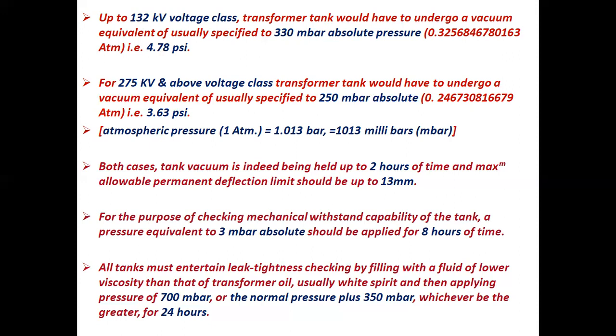In both cases, tank vacuum is to be held up to 2 hours, and the maximum allowable permanent deflection limit should be up to 13 millimeter. For the purpose of checking mechanical withstand capability of the tank, a pressure equivalent to 3 mbar absolute should be applied for 8 hours. All tanks must undergo leak tightness checking by filling with a fluid of lower viscosity than that of transformer oil, usually white spirit, and then applying pressure of 700 mbar or the normal pressure plus 350 mbar, whichever be the greater, for 24 hours.